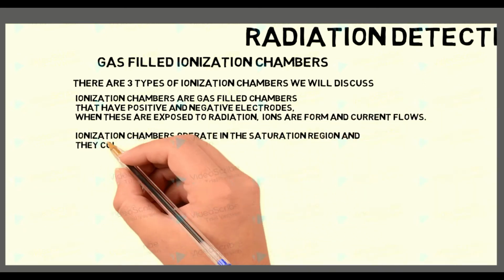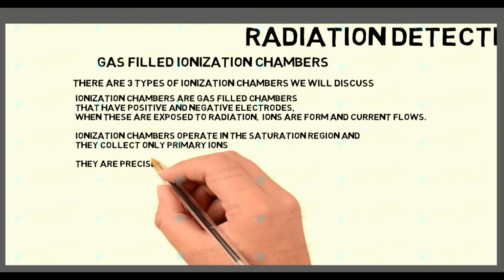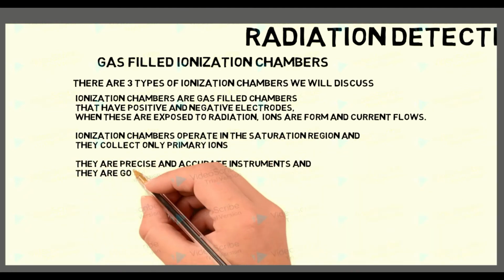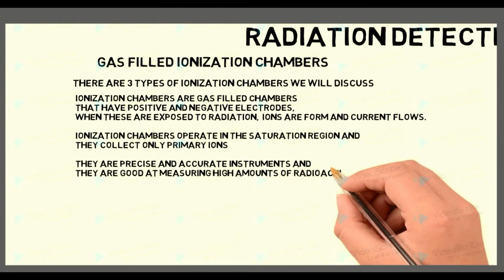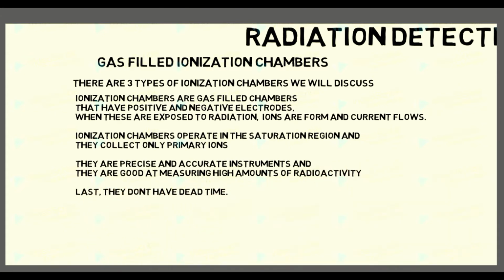Ionization chambers operate in the saturation region and they only collect primary ions. They are precise and accurate instruments, and they are good at measuring high amounts of radioactivity. Last, they don't have dead time.